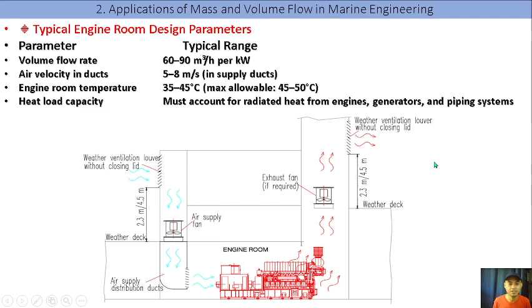Okay, problem solving. One two-stroke main engine rated at 8,000 kilowatts with 2 auxiliary engines at 1,000 kilowatts each. Total is 8,000 plus 2,000, equal to 10,000 kilowatts. Multiply 10,000 kilowatts by the volume, which is 70 cubic meter per hour per kilowatt, giving you 700,000 cubic meter per hour. Convert that per hour value to per second, giving 194.4 cubic meter per second.